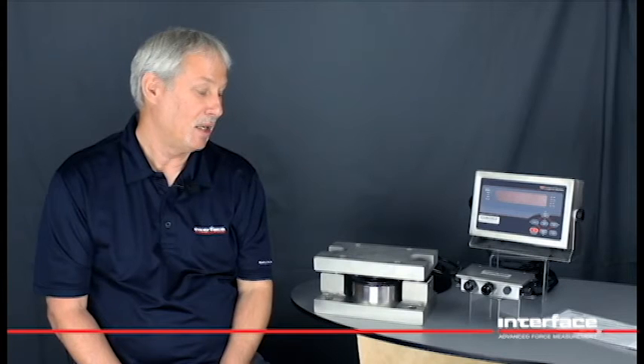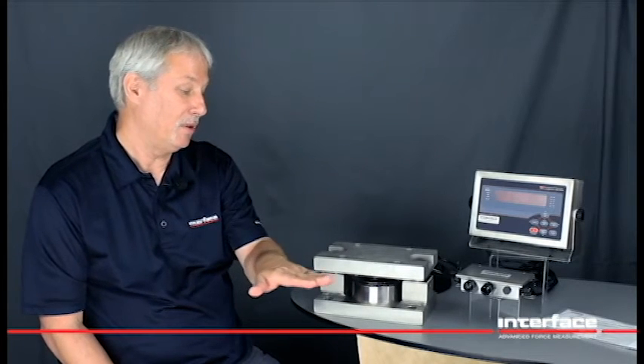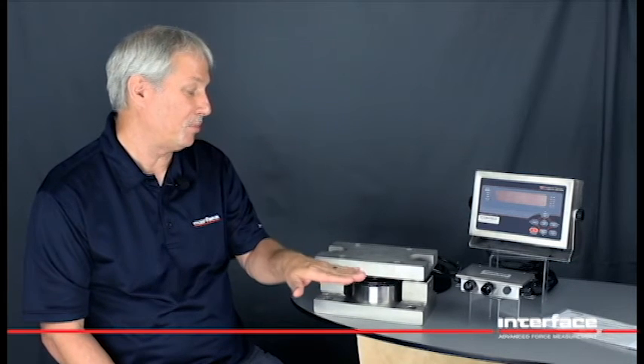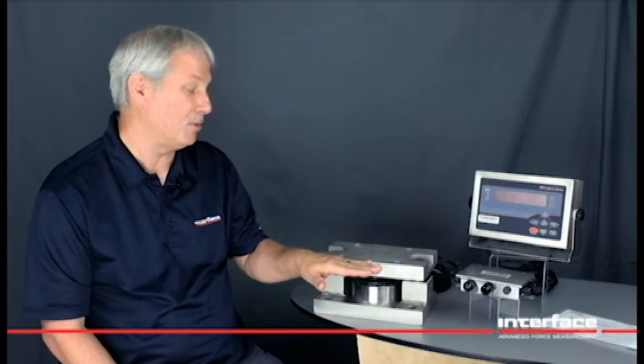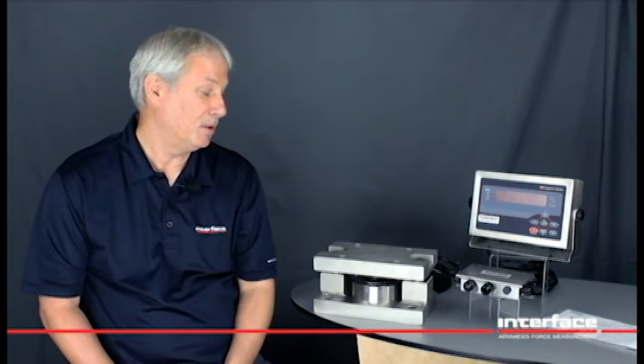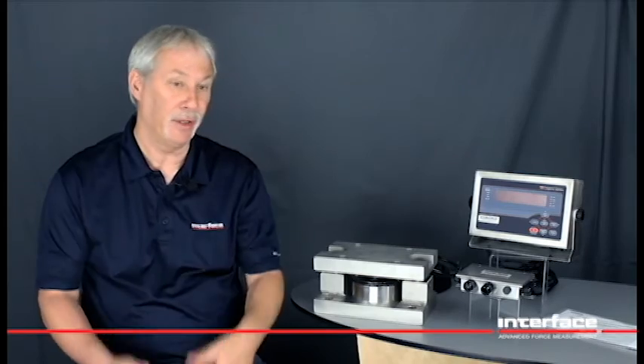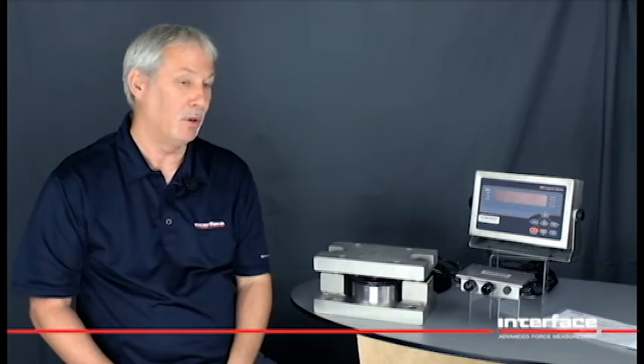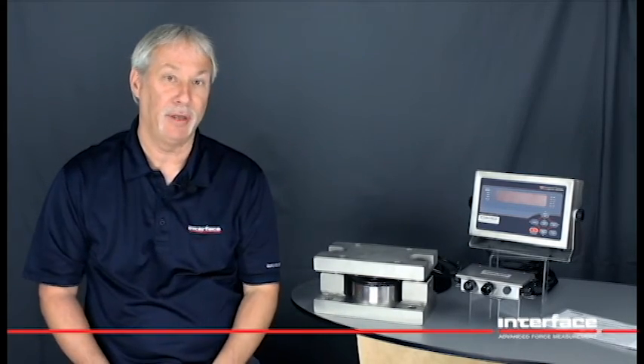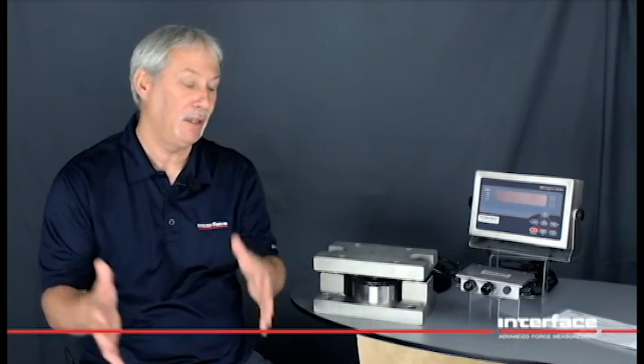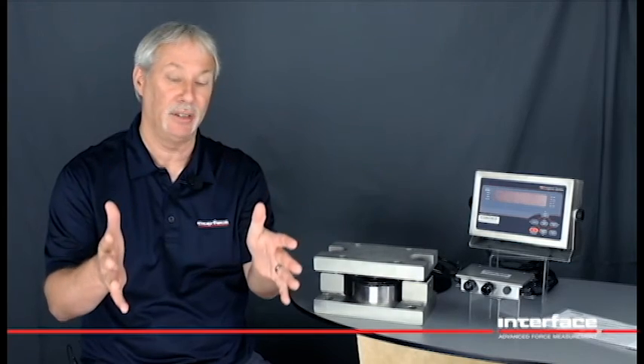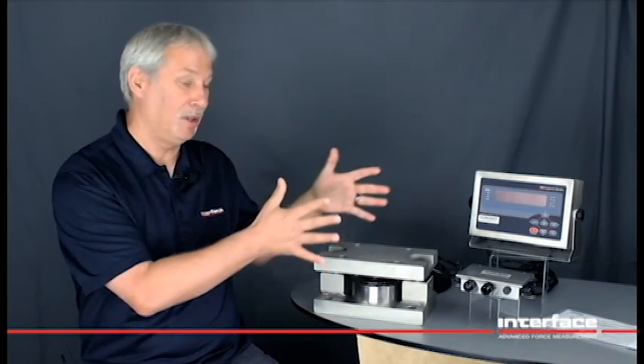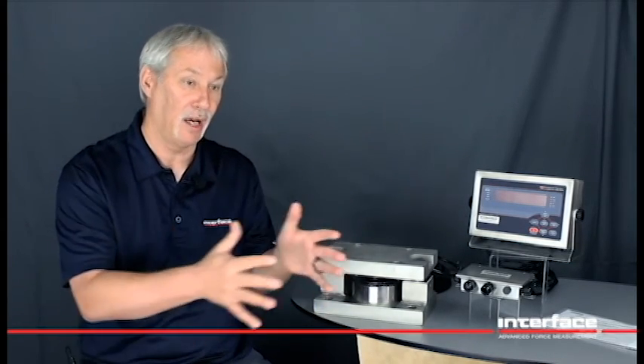A side load is when the weight and the force is applied in a lateral direction. This can happen during installation or it can also happen if there's seismic activity and the material in the tank or vessel shifts from side to side.